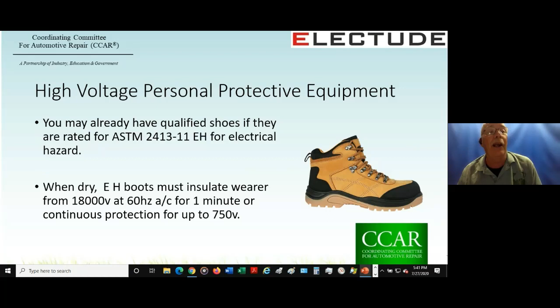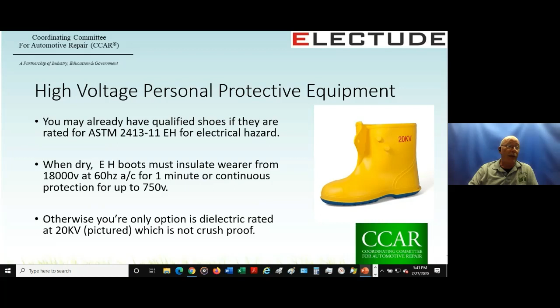Now, some of you may already have PPE that qualifies. You may not even know it. You may already have qualified shoes if they meet ASTM 2413-11 EH for electric hazard, which simply states that when the boots are dry, and the keyword here is dry, folks, EH boots must insulate the wearer from 18,000 volts at 60 hertz AC for 1 minute, or a continuous protection rating of up to 750 volts. Otherwise, your only option is the dielectric boot. The dielectric boot is a wonderful boot because it's rated for 20,000 volts, but it is not steel-toed, steel-shanked, and has no metatarsal guards. It's simply an overshoe, not crush-proof on any front.